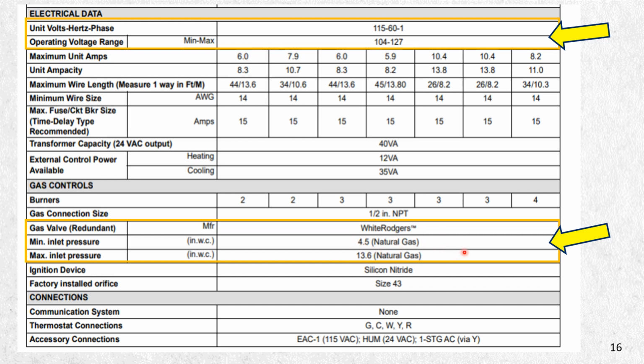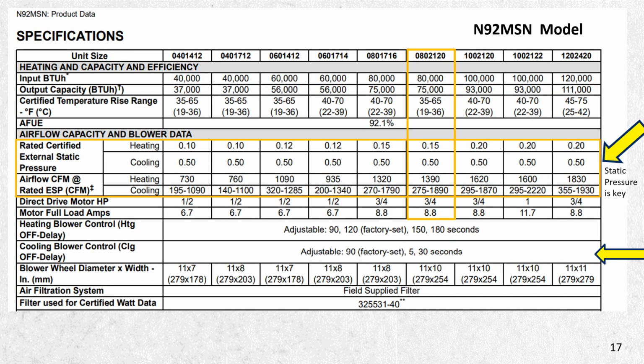Then I also want to look at the gas valve. It has a minimum inlet pressure of 4.5, and a maximum inlet of 13.6. So keep that in mind when you're setting your gas pressure. Now the one that we're showing off is the N92MSN, and it is an 080-2120. And our heat needs to be set at 0.15 static, and in cooling 0.50 static. Okay.